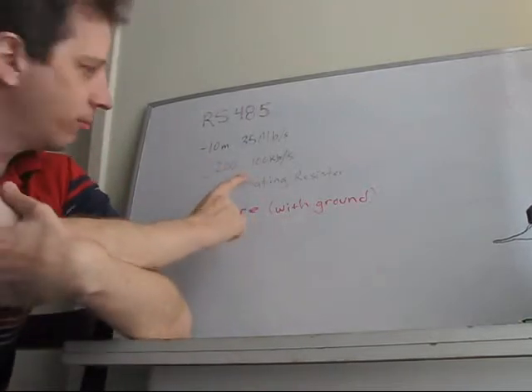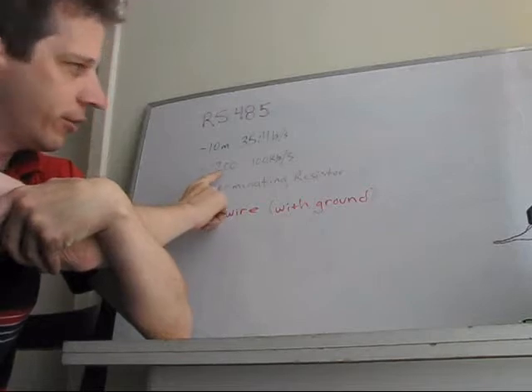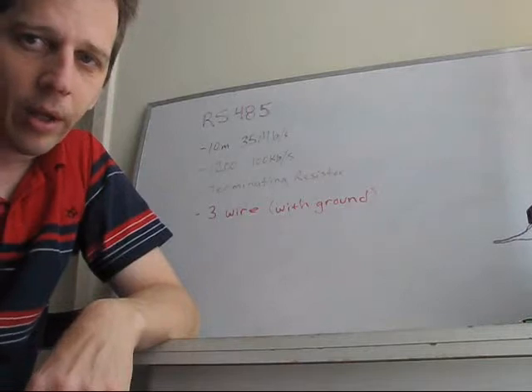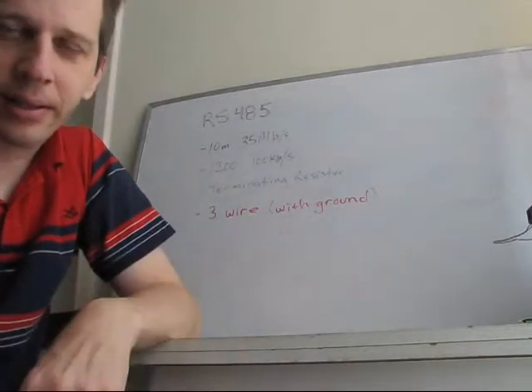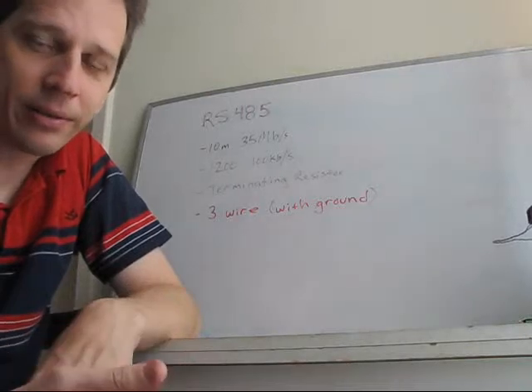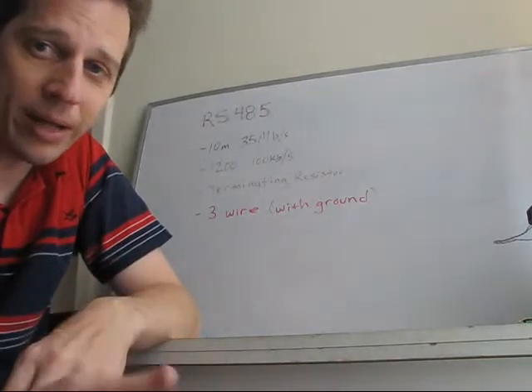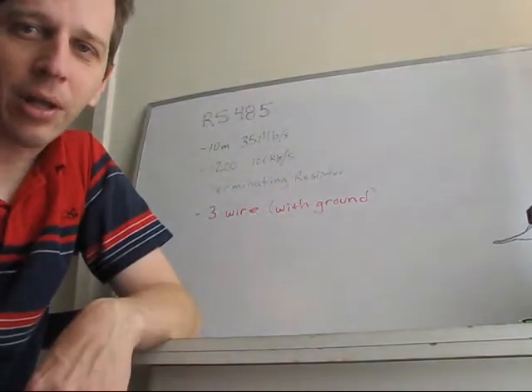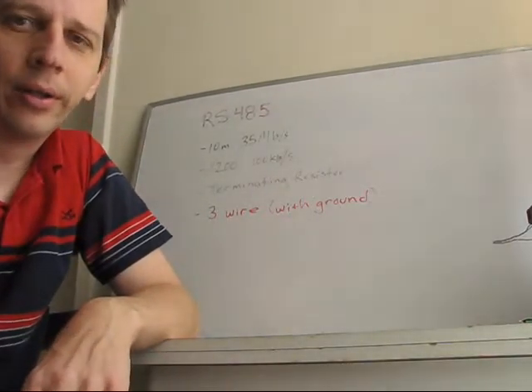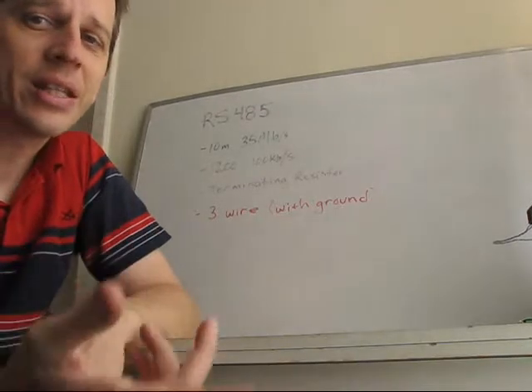But look at this, the really interesting thing here, that at 1,200 meters, you can get up to 100K. 100K, not 100 megabits, which is way less than Ethernet. But again, you don't have that much data, and look how far that is, man. 1,200 meters. You know, Ethernet, you're going to get the most out of like 90 to 100. So the distance is enormous.